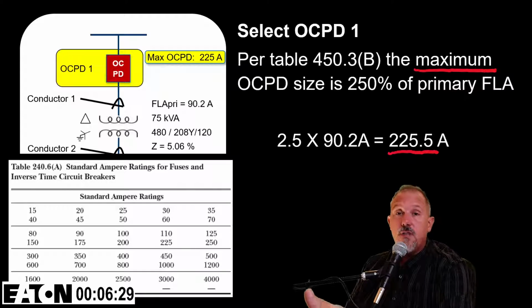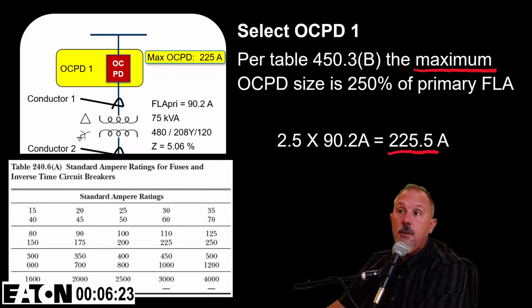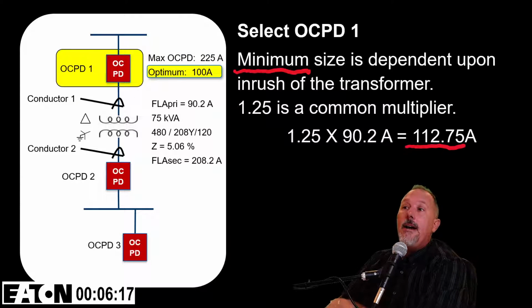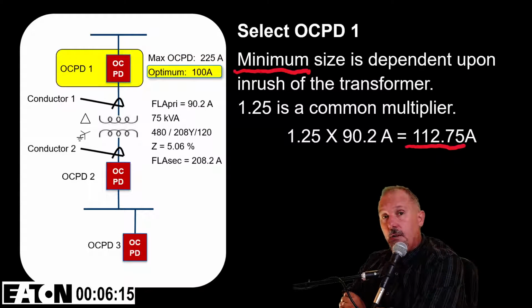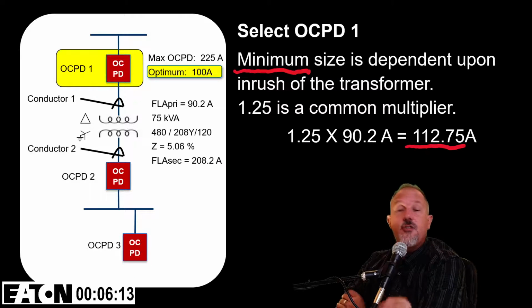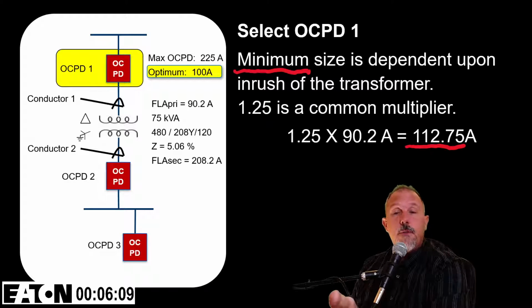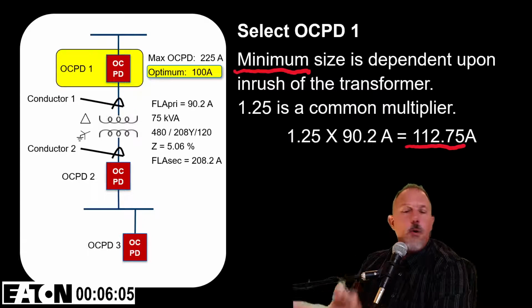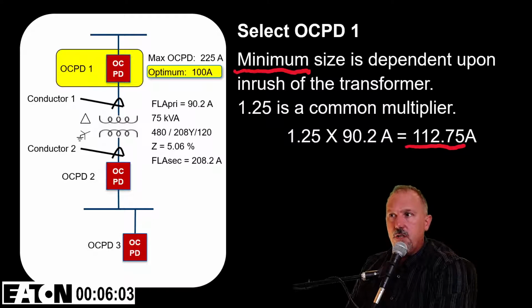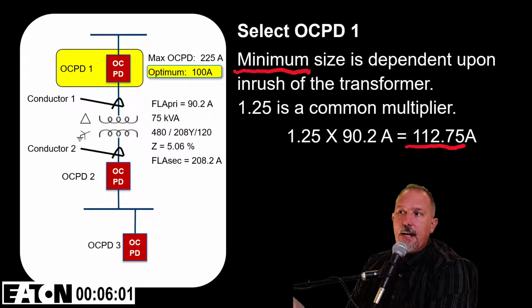Selective coordination through a transformer, which I do have a video that covers, could push that primary overcurrent protective device up to much higher than what you would probably feel comfortable in a normal application. Now, the minimum size overcurrent protective device on the primary is going to be driven not by multiplying factors. It's more so going to be driven by the inrush of the transformer. So a 1.25, again, is a common multiplier. And if I use that, I get 112.75.